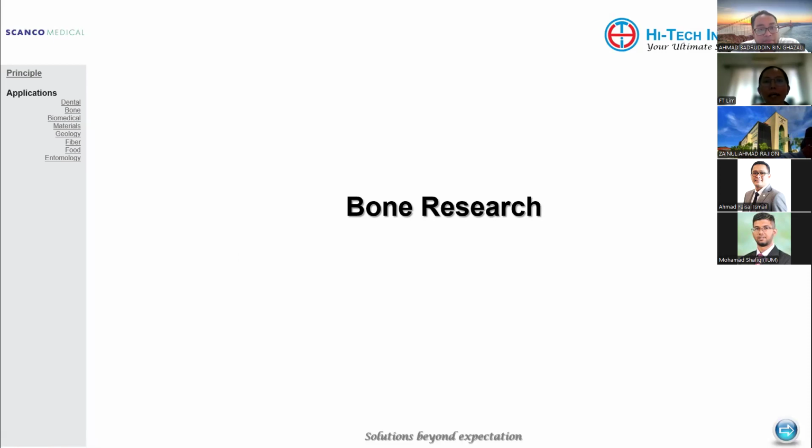Okay, as I mentioned earlier, we have three types: ex vivo, in vivo for animal, and patient clinical. For the ex vivo and in vivo, we do not need the shield because it's fully covered, fully shielded. So we can guarantee that the minimum amount of radiation that you can detect is like 5 cm away from the scanner itself.